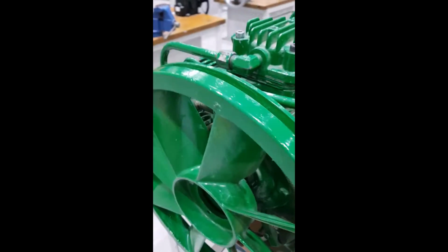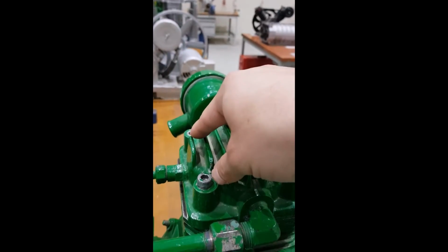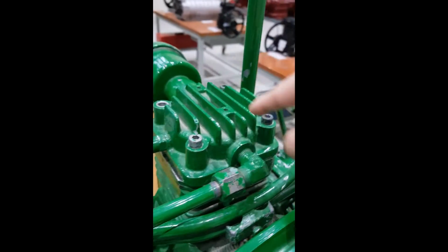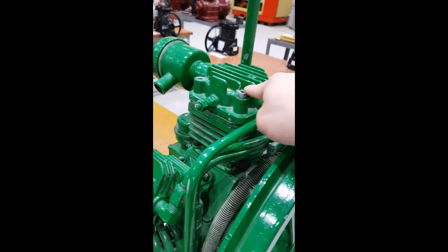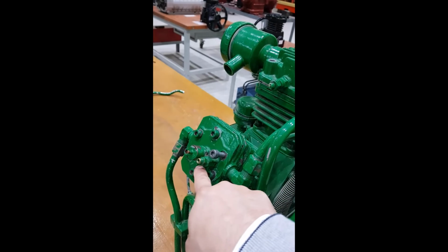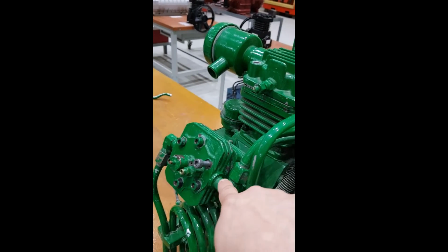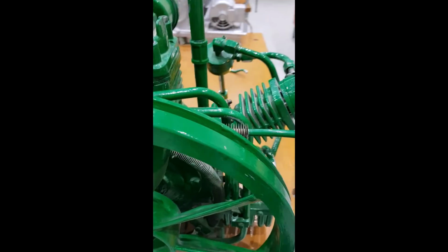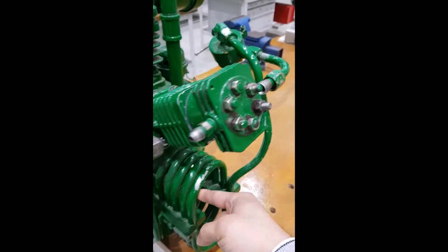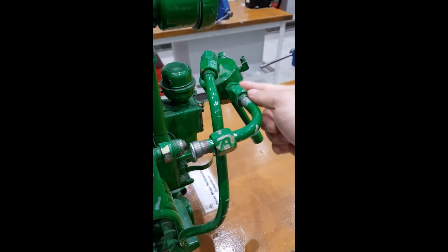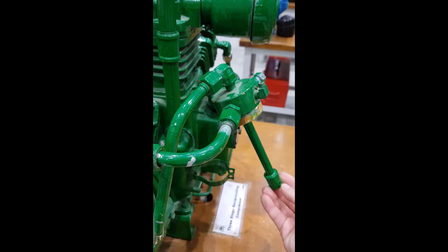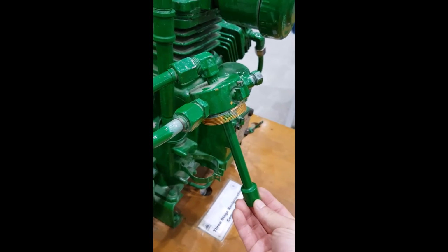So what happens is that in the first stage, when air enters, it will enter cylinder block number 1, which is considered to be the LPC. From there, after they get compressed, they will move through the tube intercooler to the second stage. They will get compressed again, then move through the tube intercooler again over here. But before they go to the third stage, they will go to something called a moisture separator. There must be a tank or a cup over here to isolate the moisture from the compressed gas.